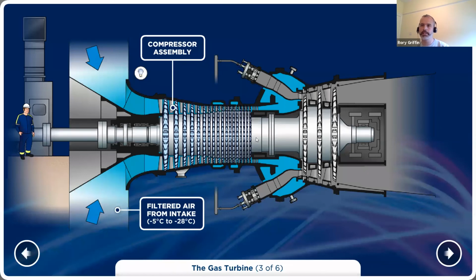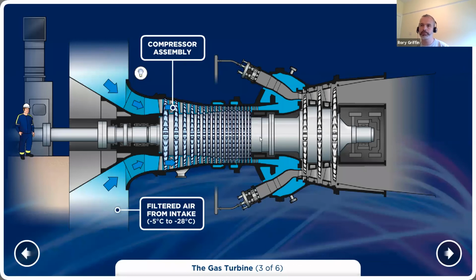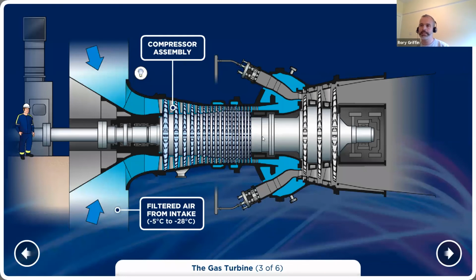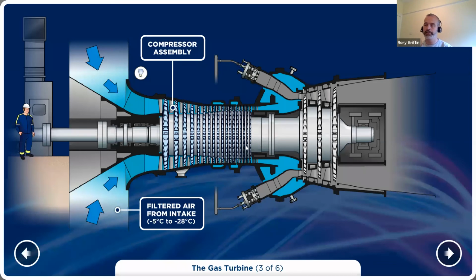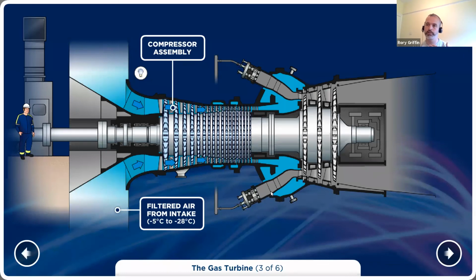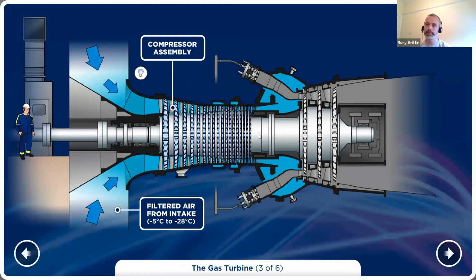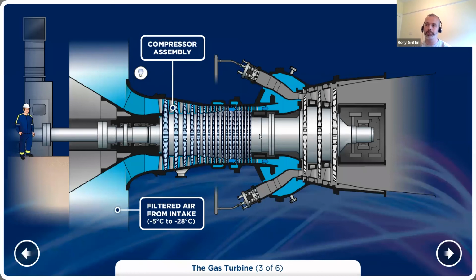which is the design. But what we're seeing is more and more discussions about what's happening when the frequency isn't quite at 50 hertz. On the flip side, if the frequency is very high, your machine will speed up, you'll pull more air in, the governor on the machine will try to back off the gas, and you run the risk of getting a bit lean. Worst case scenario, you get a lean blowout, you'll extinguish the flame and the unit will trip. So these are all considerations that we had to look at when we were doing the ROCOF study.